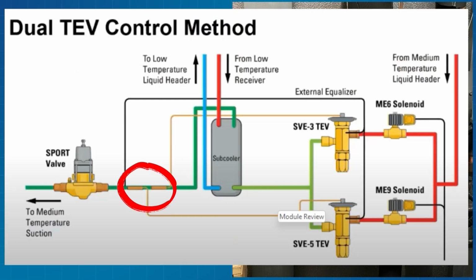When that happens, my bulb that's sensing that is not real far from that heat exchanger. And it's going to happen so fast and so much refrigerant is going to flow through there, it's possible that this is all going to be liquid until somewhere out here. That happens. We don't see that very often on a case, but we will see that regularly on a subcooler.